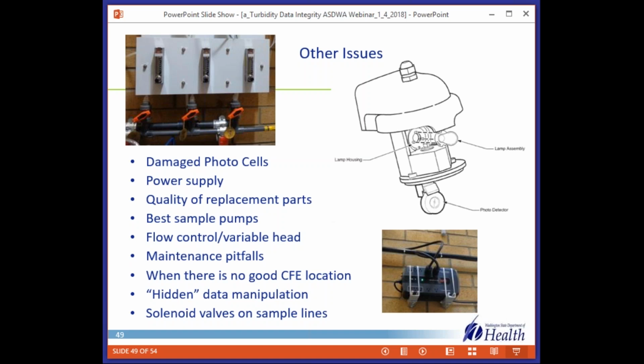Looking at power supply, we had a number of utilities where the weekly test of their generator would wreak havoc on their equipment. And so many of them installed uninterruptible power supply. But these vary all over the map. The one that's shown here is a $70 model that you can buy at the office supply store. And I think the point here is that this is much different than a system that costs 100 times as much that has a lot greater capability. So if you decide to pursue this, I would definitely talk to people who are experts in this area and make sure you're buying the kind of protection that you're looking for.